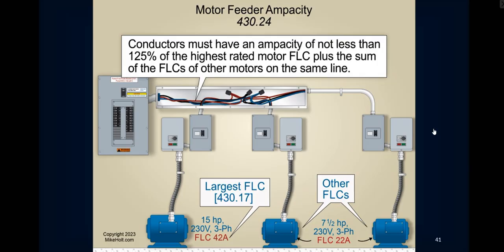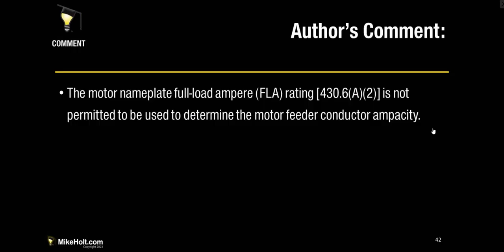Whenever we're calculating, we're determining this. I'm telling first-year students the same thing. It's all about determining the ampacity, because once I've determined the ampacity, then I can size my overcurrent protection. I can size my conductors. Then I can size what size pipe I'm running. I can build the job. So the motor nameplate FLA rating from 430.6(A)(2) is not permitted to be used to determine the motor feeder conductor ampacity. We're talking about the motor feeder.